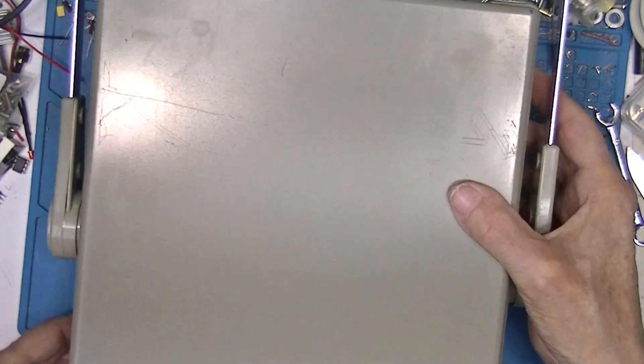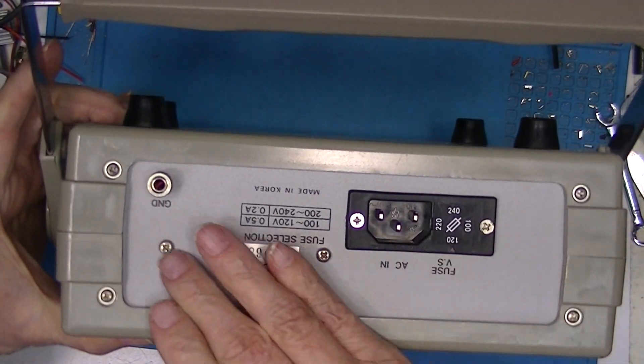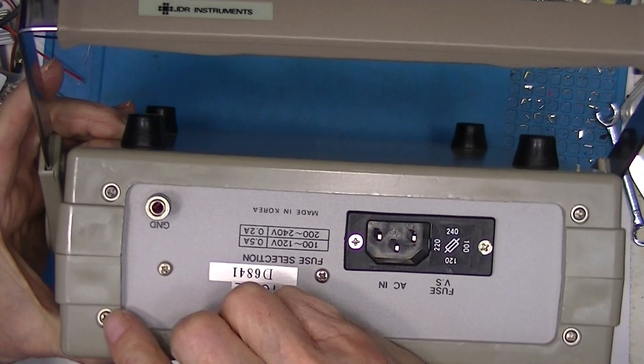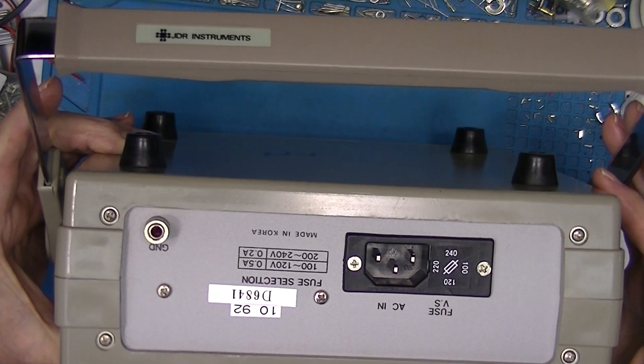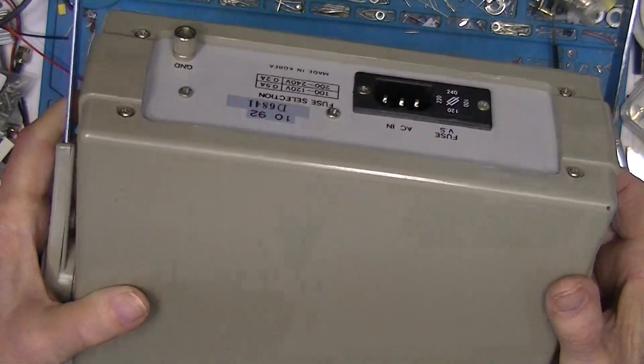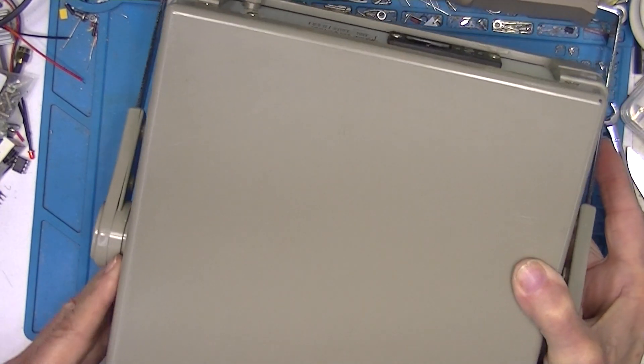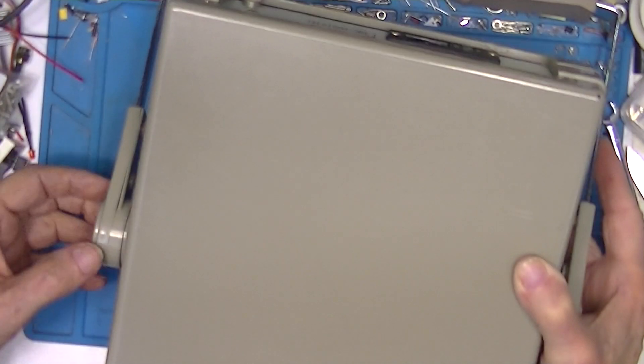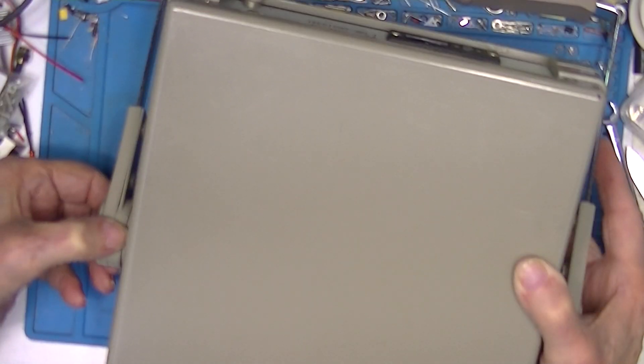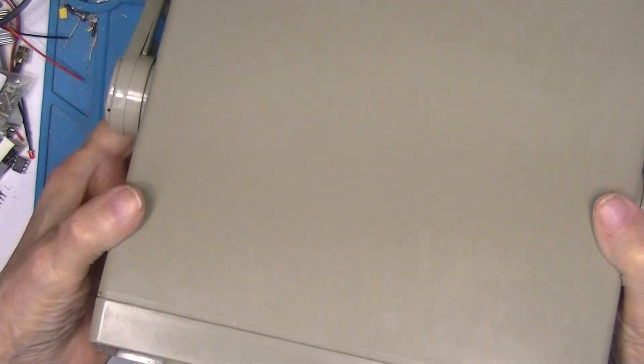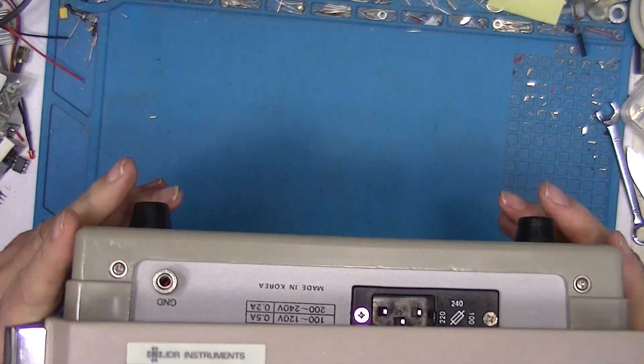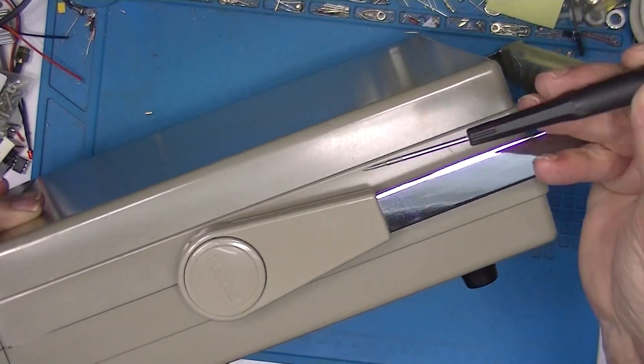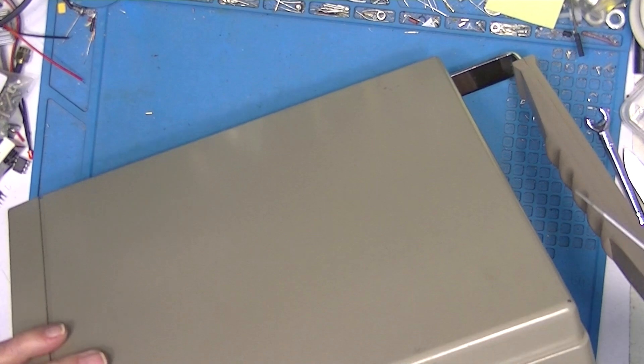Now this is an interesting thing. The case is split on the center line into a top and a bottom, and they are held on by two screws on the top, two screws in the bottom. The side of the case has a boss in it, top and bottom, and this fits over the boss. The case is not fastened in front, so we have to take these folding handles off. Pushing in allows you to rotate them with a real small tool. You find a hole.